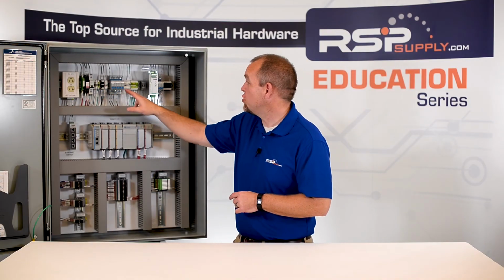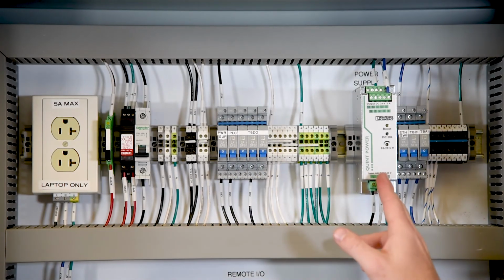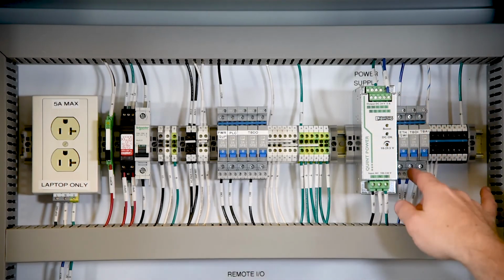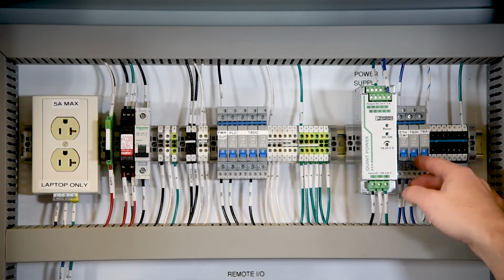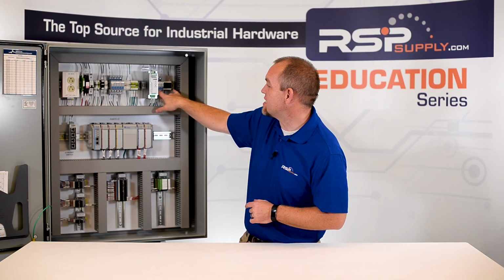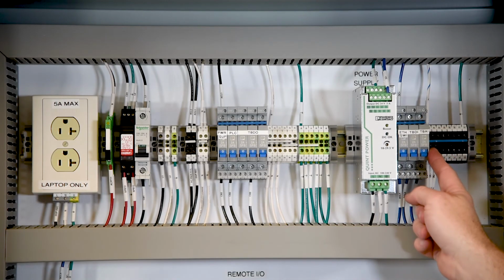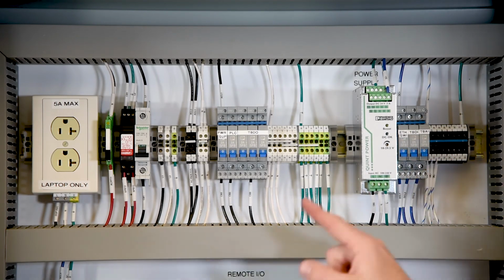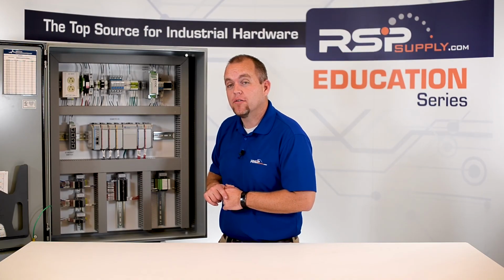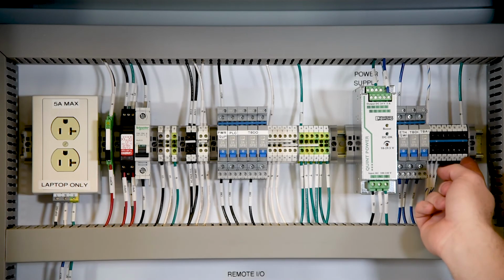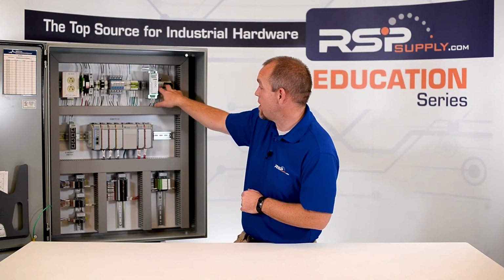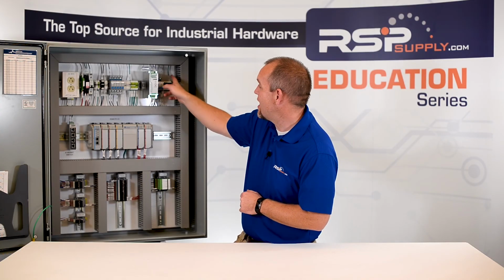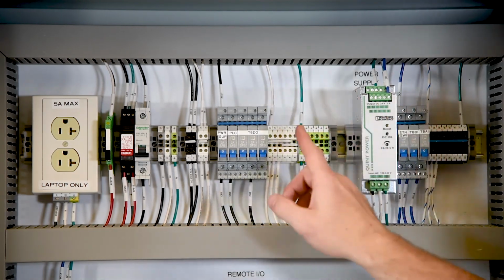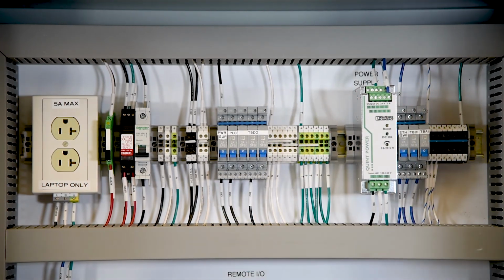Next, we move over to our power supply, which again is being supplied by our supplementary AC breakers, and then changes that power to DC power. And here you see our DC power bus. This powers any DC devices, such as our Ethernet switch or some of the IO on our industrial control panel. Again, our DC negative bus is located right next to the supplementary breakers on our DC power. And here you see our ground from DC negative to our main grounding bus.